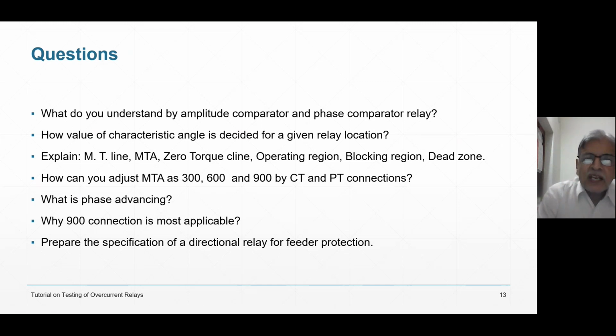How is the value of characteristic angle decided for a given relay location? Say in my power system, in Gujarat state, there are many power plants. I am at Vallabh Vidyanagar, and there is a 66 or 132 kV bus. There I want to have a directional relay. So what should be the characteristic angle of that directional relay? How will you decide? What is the equation? What are the methods? How can you calculate that?